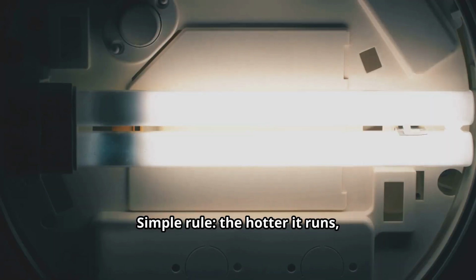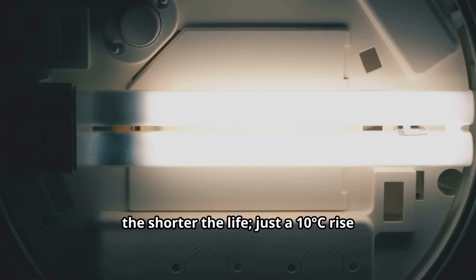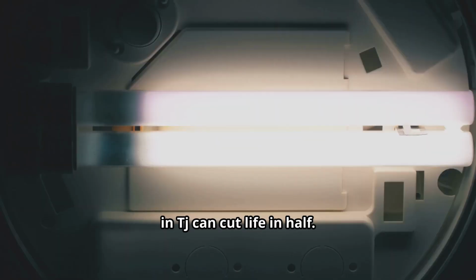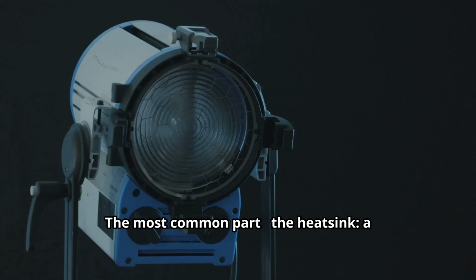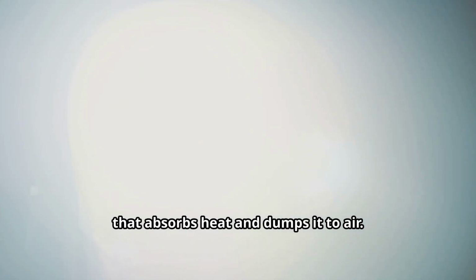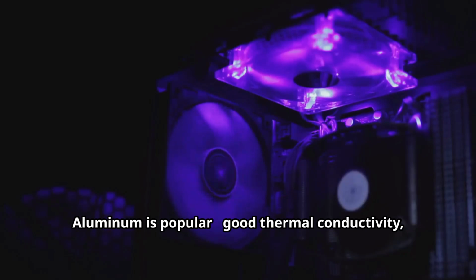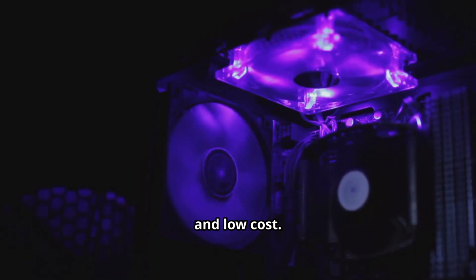Simple rule: the hotter it runs, the shorter the life. Just a 10 degrees C rise in TJ can cut life in half. The most common part, the heatsink, a passive heat exchanger, usually aluminum, that absorbs heat and dumps it to air. Aluminum is popular. Good thermal conductivity, lightweight, and low cost.